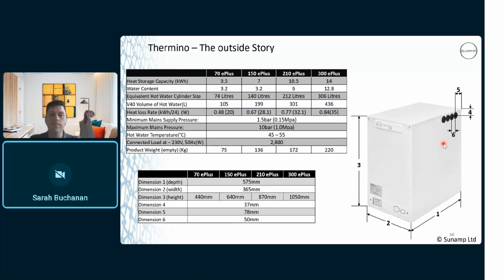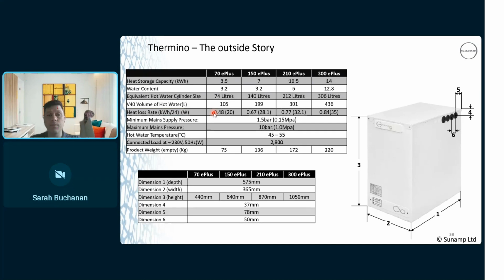Does the phase change material fully discharge over time? It will do, yes, due to the standing heat loss rate. If you use the calculation for the 70, divided by your heat loss calculation, it will take 7 days to fully lose its heat and fully discharge itself. So essentially you could fully charge a 70, go away for the weekend, turn it off at the timer, and come back and still have hot water there.